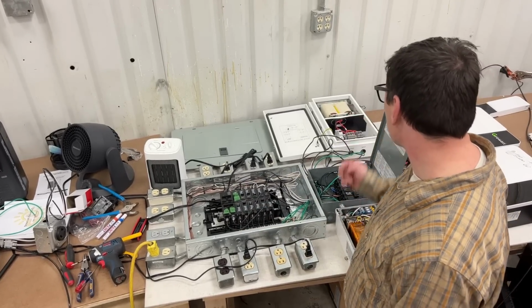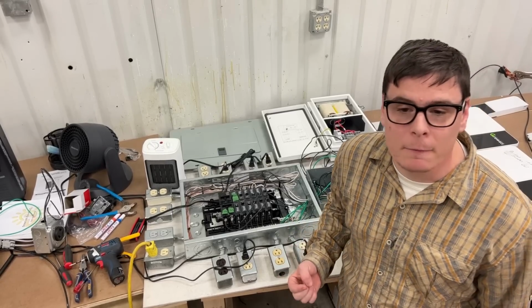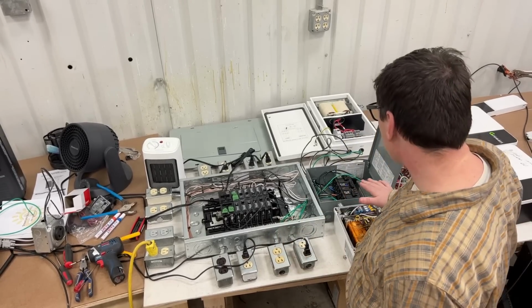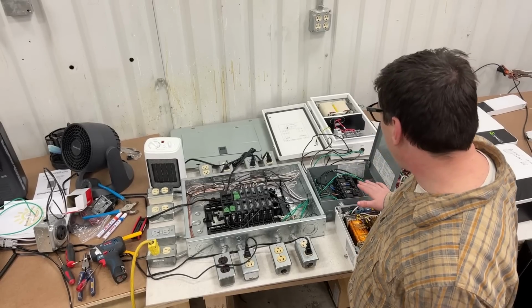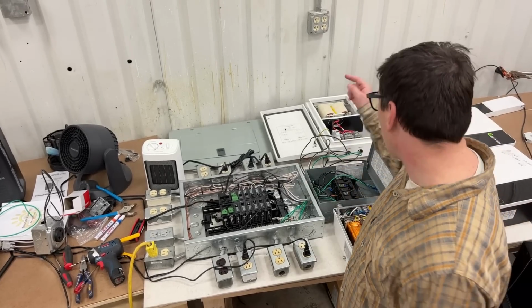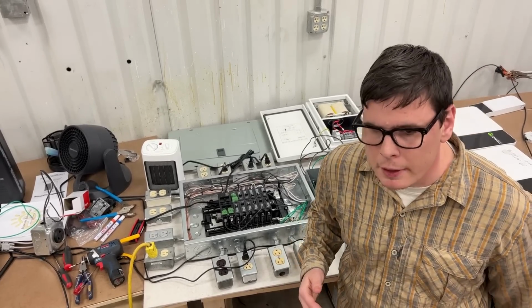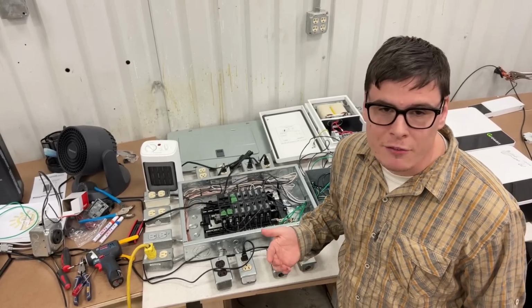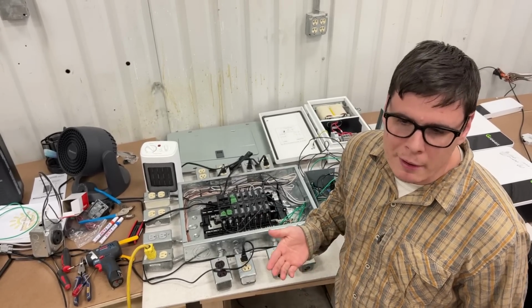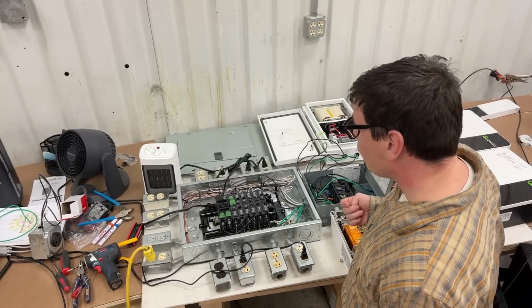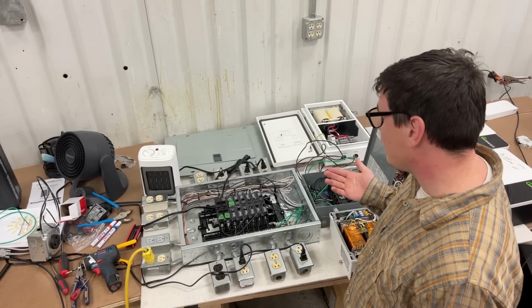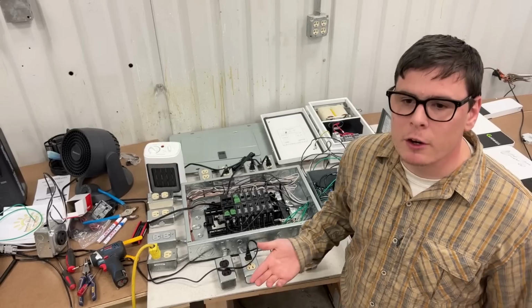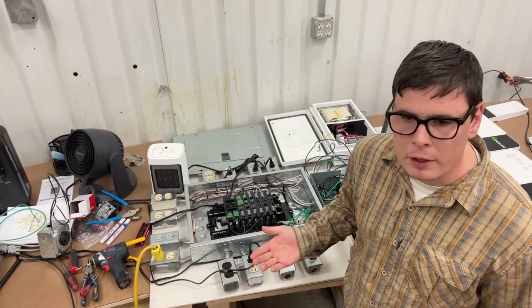So I got one of our SolarEdge from last year. That's a 25 amp breaker on that transformer. It's what it recommends. So I've landed that on a 25 amp breaker. If I'm using the new Growatt ones, that's a 20 amp breaker. Now, if my main combined breaker panel had 2 transformers, a Growatt and a SolarEdge, then I'd be looking for 45 amps. I'd probably just say we can get away with 50. Because what you're going to find out here is that this is going to provide the level of overcurrent protection that will protect your 120 volt devices.